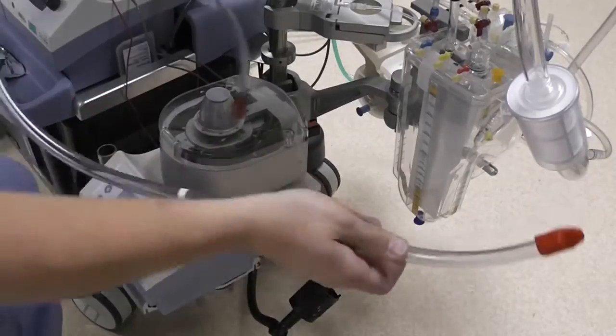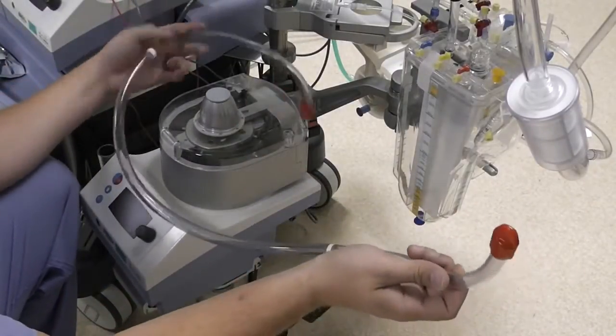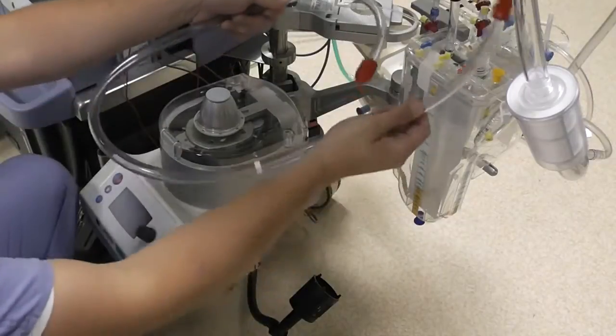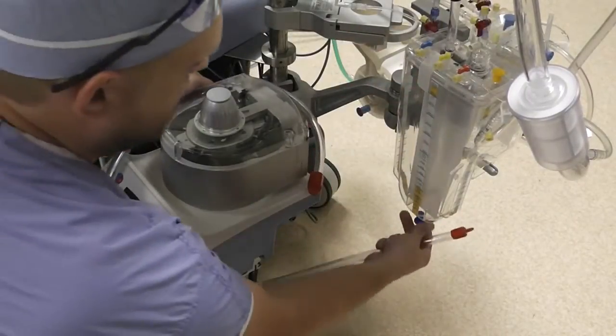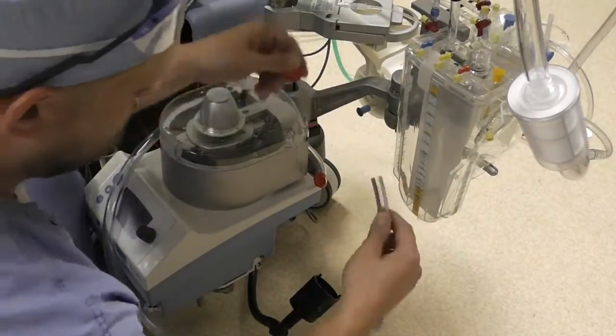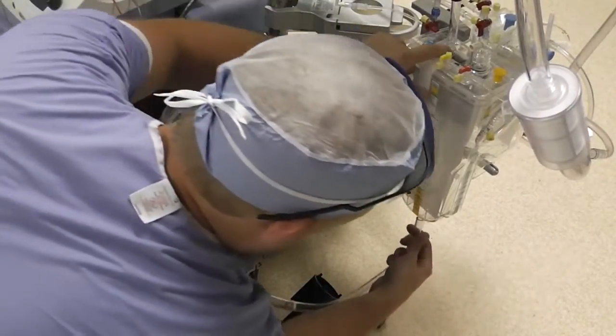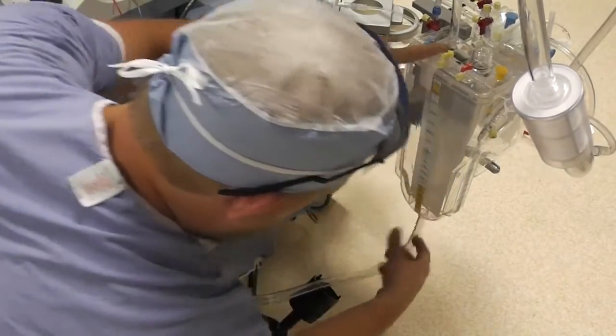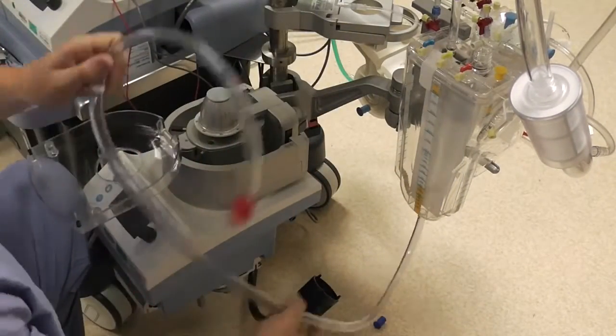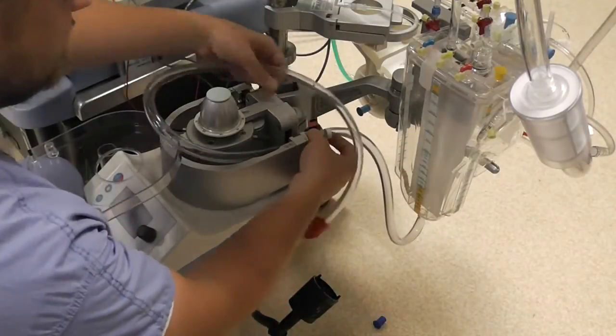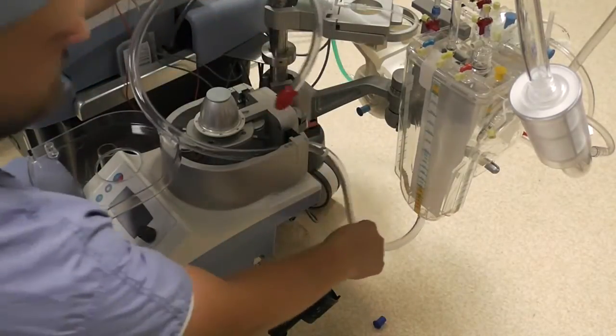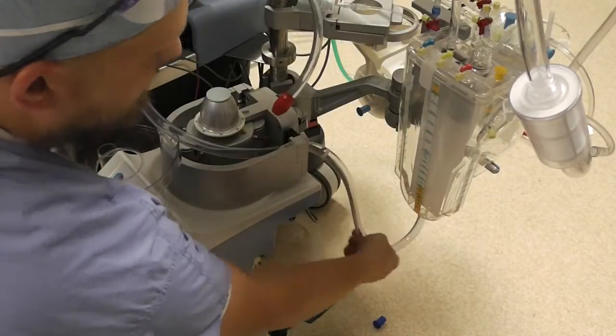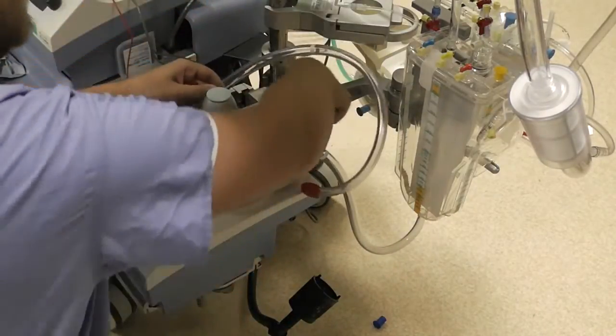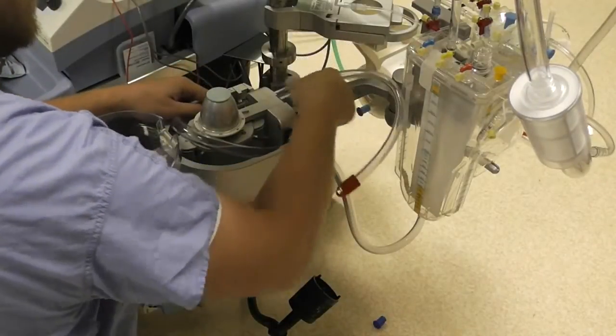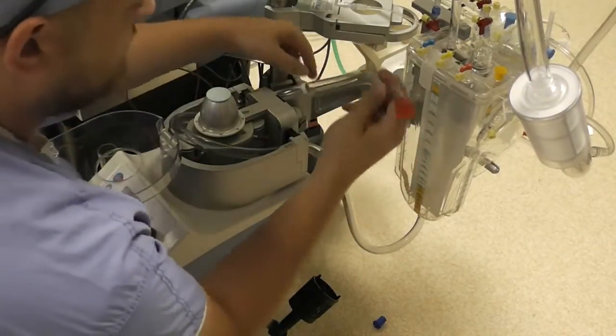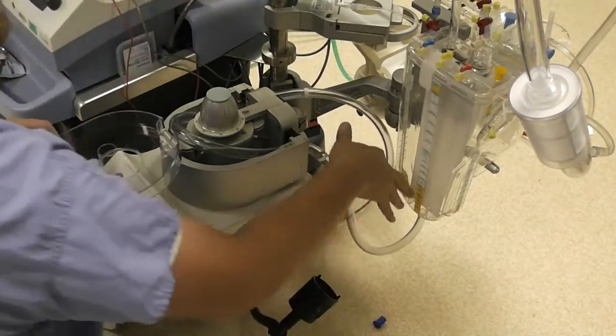Alright, so we're going to try to find sort of the natural curvature of this line. You can kind of see how it wants to lay. And we're going to make the connection to the bottom of the reservoir. Open up the pump head here. Sit the line inside the head. Close that connection, making sure that this line isn't kinked anywhere. Wrap it around the head to the other side, and now this free end is going to attach to the oxygenator.